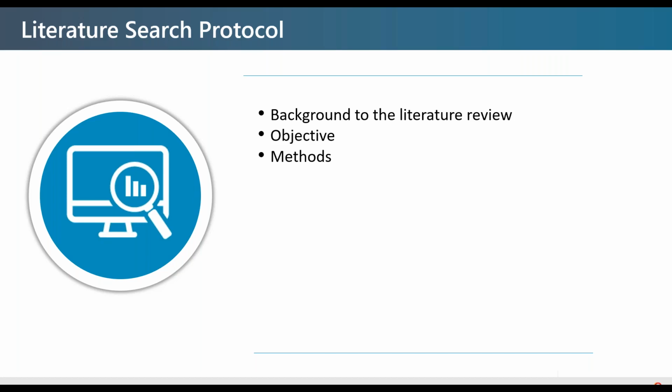So this will apply to both clinical data as well as state-of-the-art. The guidance says it has to be methodologically sound and repeatable. And believe me, the notified body has come in and taken my search criteria and they have tried to repeat it, and they want to see what your output was and make sure that you aren't cherry picking the data to show only the good.